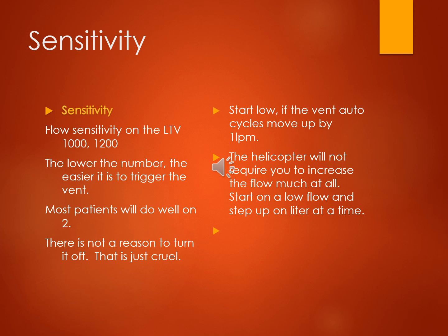An auto cycle is when the ventilator, as the lungs close or semi-close, they create a negative deflection, which actually could cause the ventilator to trigger again. You could also have water in the circuit that was sloshing back and forth that can cause another trigger. So make sure the circuit is not dry, but there's no water sloshing, and then that it's not auto cycling. But then if you are auto cycling, just go up by one at a time until the patient is able to cycle on their own and it's not auto cycling.